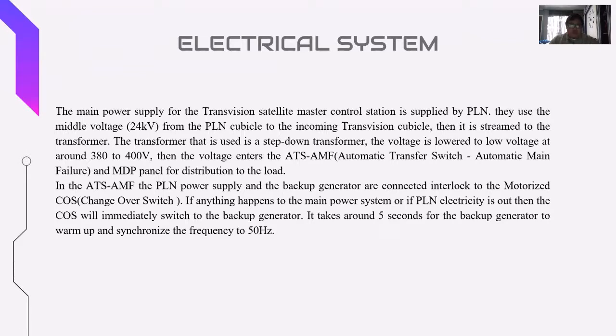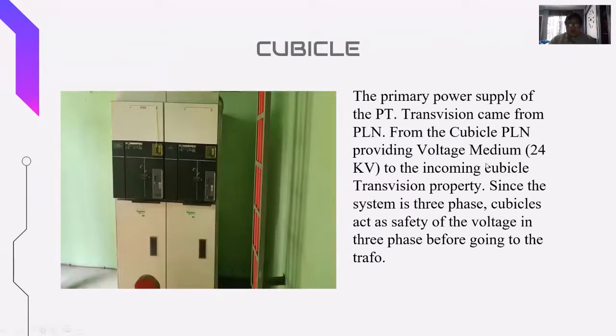In the ATS AMF, the PLN power supply and the backup generator are connected, interlocked to the motorized COS. If anything happens to the main power system, or if the PLN electricity is out, then the COS will immediately switch to the backup generator. It takes 5 seconds for the backup generator to warm up and synchronize the frequency to 50 Hertz. And the cubicle is basically a safety for the voltage because the system is 3-phase. So when the incoming electricity is too big, they might trip. So the cubicle will anticipate it and short circuit it or discard it.